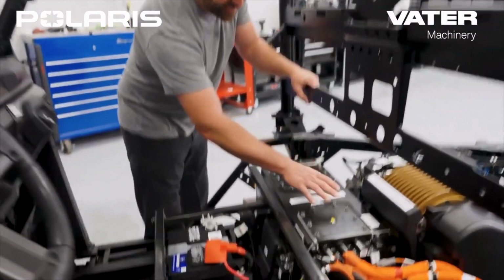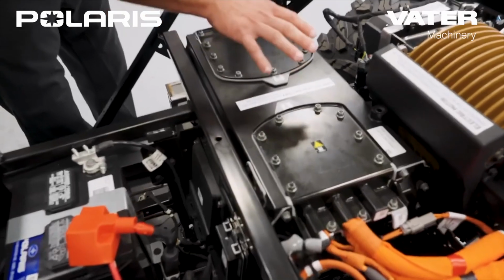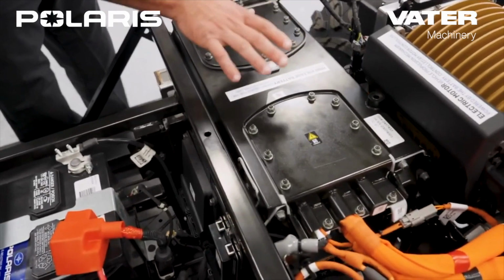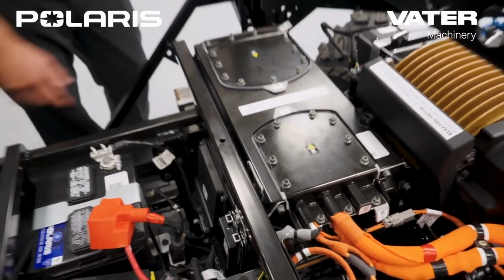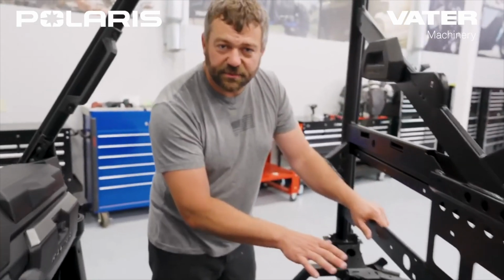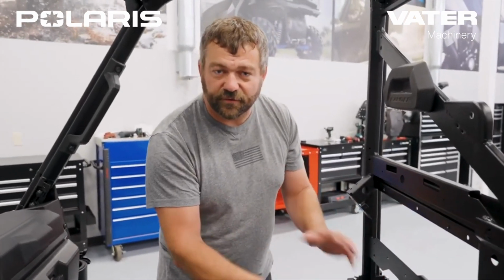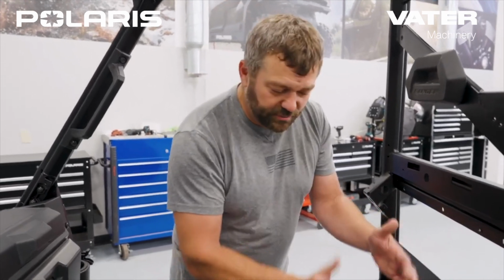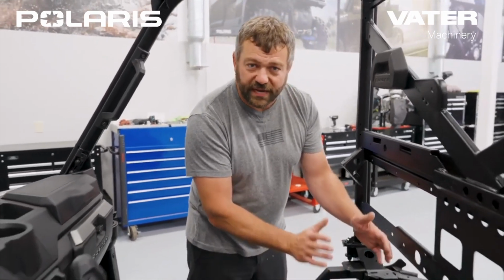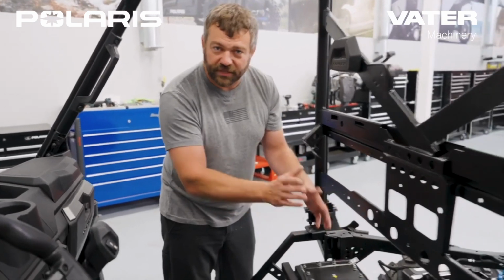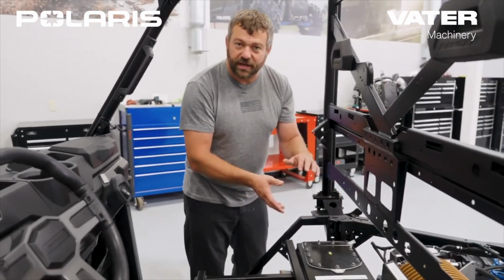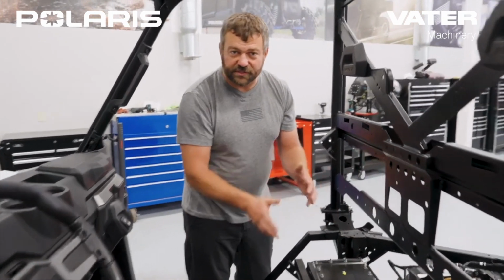The other thing inside of this is a battery management system controller, along with current sensing, hydrogen sensing, and a couple other things. The cool thing is it's able to monitor the cell health and adjust the current flowing in and out of the battery automatically, so you don't have to worry about it. That balances the two halves of the battery pack so you get an equal amount of power flowing in and out of each one, so you're not overstraining one half versus the other.